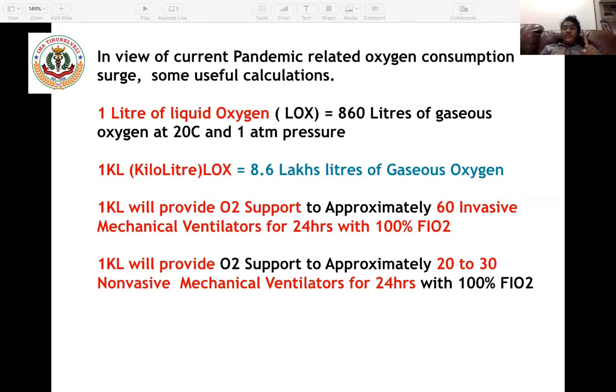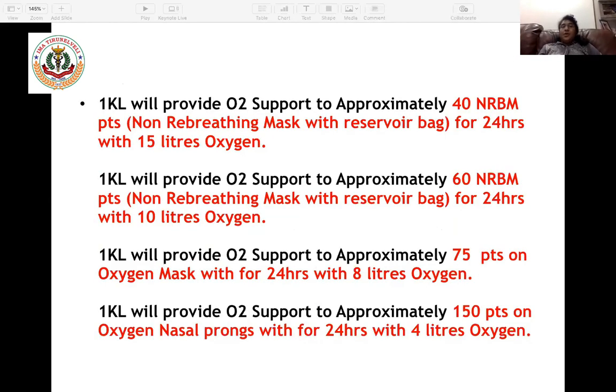1 liter of liquid oxygen is equivalent to 860 liters of gaseous oxygen at 20 degrees Celsius and 1 atmospheric pressure. 1 KL is equivalent to 8.6 lakh liters of gaseous oxygen. 1 KL will provide oxygen support to approximately 60 invasive mechanical ventilators for 24 hours with 100% FiO2. At the same time, 1 KL will provide 20 to 30 non-invasive mechanical ventilators for 24 hours with 100% FiO2.